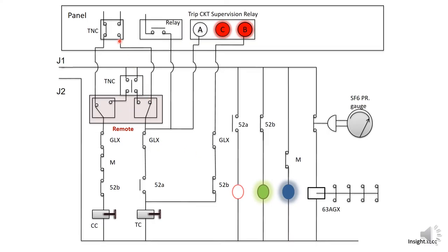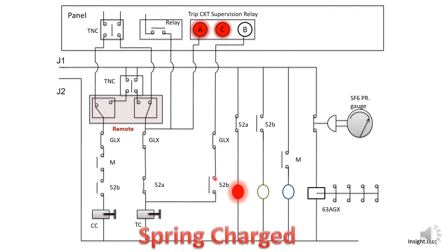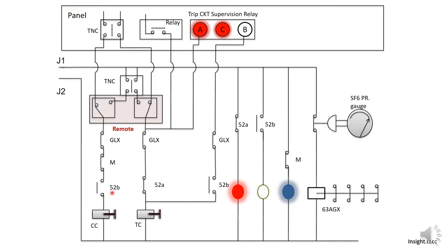When the TNC command is given, all the contacts will change their position. The spring charge contact will be closed, and 52A and 52B will change their position. So if 52A is closed, then in post-close supervision, the A-coil is operated and the C-coil is operated.